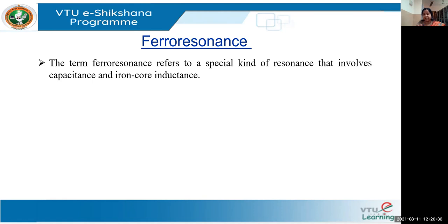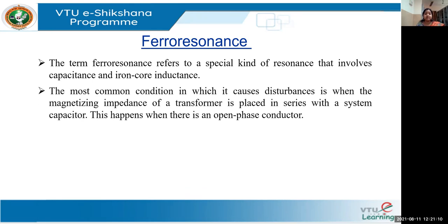Ferroresonance is a special kind of resonance that involves the inductance of the transformer when it comes in series with capacitance. It happens basically in a non-linear kind of inductance. The circuit contains a non-linear type of inductance in series with the effect of capacitance. When I talk about a non-linear inductance, I'm talking about a transformer or reactors. The most common condition causing disturbances is when the magnetizing impedance of the transformer comes in series with the capacitance effect.